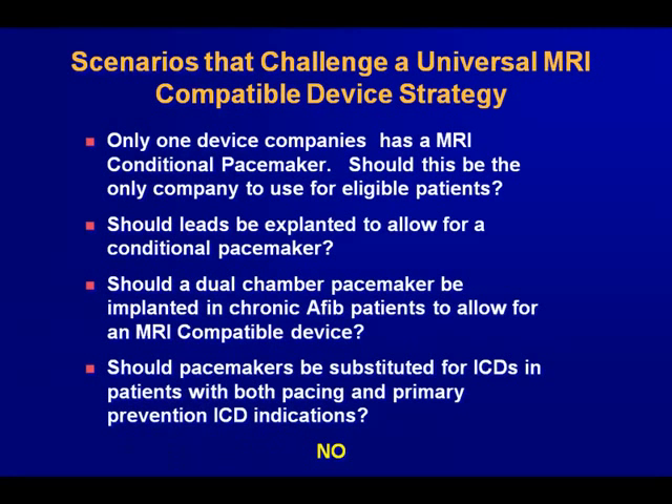There are a number of scenarios that challenge a universal MRI-compatible device strategy. Only one device company has an MRI-conditional pacemaker — should this be the only company used for eligible patients? Should leads be explanted to allow for a conditional pacemaker? Hopefully no one will subject patients to the risk of lead extraction simply because you need an MRI. Should a dual-chamber pacemaker be implanted in patients who really only need a single-chamber device just to say you put in an MRI-safe pacemaker? And should pacemakers be substituted for ICDs in patients with both pacing and primary prevention indications just to put in an MRI-safe system? Hopefully we would all agree the answer is no.